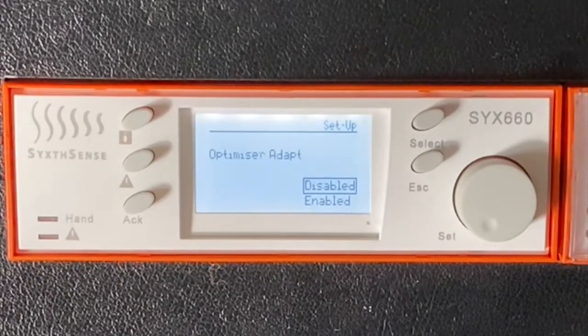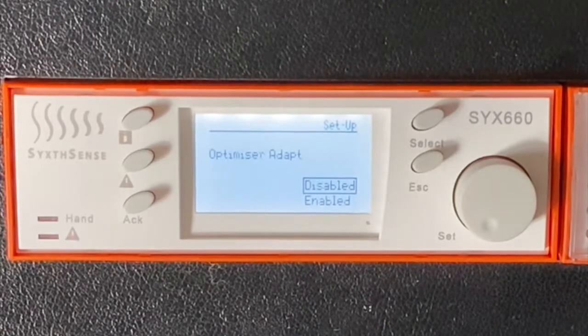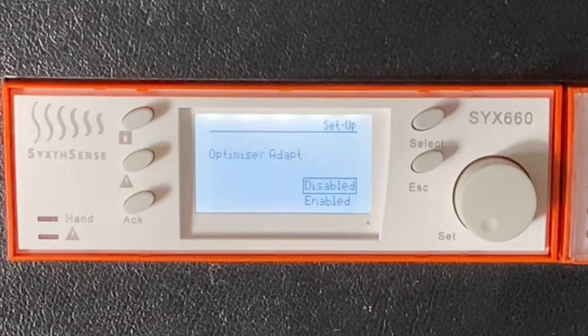We can monitor the optimizer performance on the SYX controller by going into the heating menu, into values, temperature control, and looking at the building warm-up rate. This is a factor that the controller calculates based around the current conditions and how the building is warming up based around the available heat supply into the building.